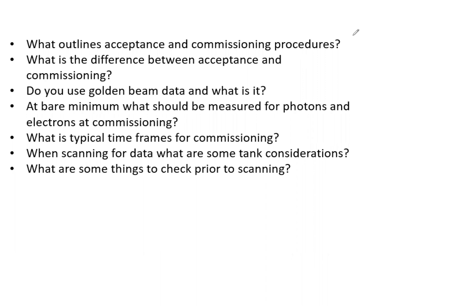TG106 covers everything we need to know about acceptance and commissioning, so reference that right off the bat and read it if you haven't. Acceptance is done by the vendor with a physicist present and requires signatures — these are essentially tests that ensure the machine you purchased is up to the vendor's specifications and tolerances. Commissioning, on the other hand, is the data you put into the treatment planning system, performed by the physicist prior to clinical release of the machine or software.